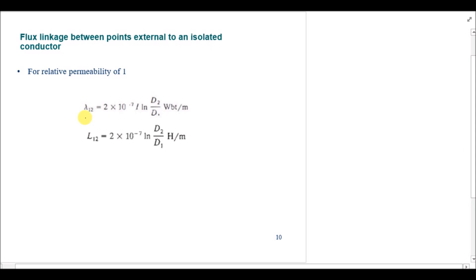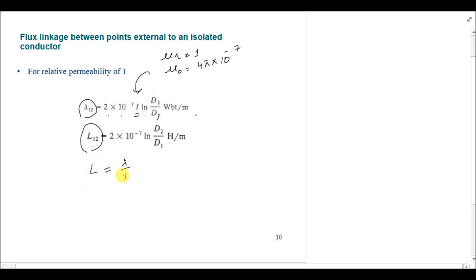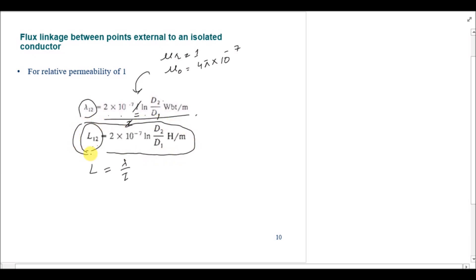Substituting the relative permeability mu_r = 1 and mu_0 = 4*pi × 10^-7, the flux linkage formula becomes: lambda_12 = 2 × 10^-7 * I * ln(d2 / d1) Weber per meter. To find the inductance between these two external points, we divide by I: L_12 = lambda / I = 2 × 10^-7 * ln(d2 / d1) H/m. This is the inductance due to flux linkage between two points external to an isolated conductor.